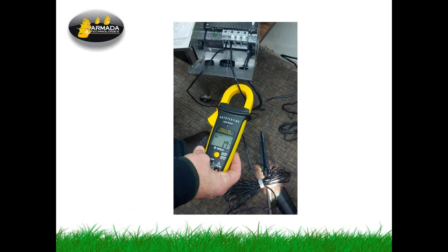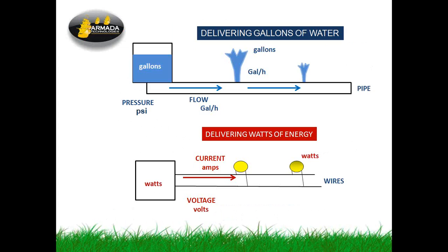The photograph here shows the Pro90 in use. Someone is using it to measure the amount of power being delivered to a lighting string from a transformer unit. It's a very common way of determining how well loaded the system is and using the clamp function. When you're using the clamp function, you don't need the test leads attached to it, which in that photo was the case. There was no test lead connected.